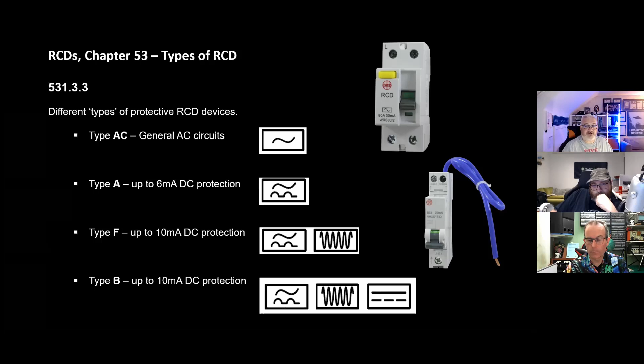Moving on very quickly, again, I made this error yesterday, apologies. Regulation 531.3.3, note 3: for general purposes only type A RCDs may be used. So you can see we are now moving away from the AC type. It then says type AC RCDs shall only be used to serve fixed equipment, not portable, where it is known that the load contains no DC components. See note 4. Now that error is still in there. It's my fault because it was note 4 when I looked at it and then it changed. Note 2: examples of fixed equipment containing no DC components may include, but not be limited to, electric heating appliances, resistive loads, and/or simple filament lighting, which my dad still has, but does not include electronic transformers or dimmers. So finally, we got a bit more clear guidance, really.